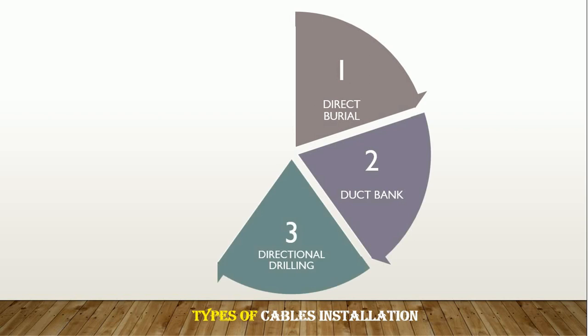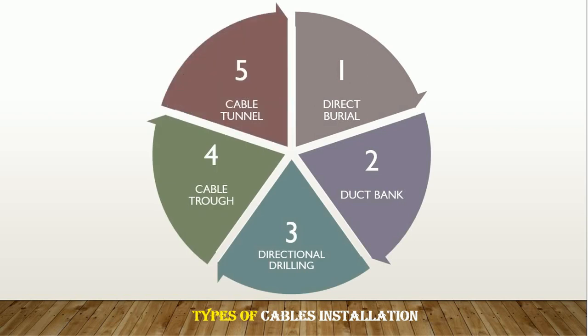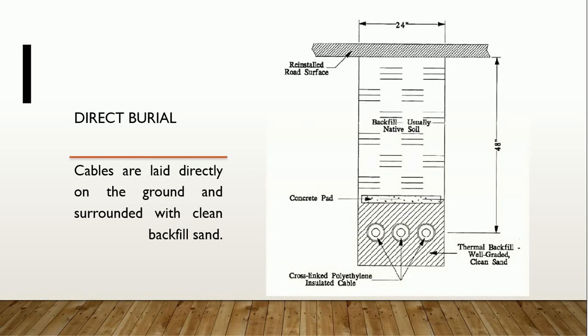Direct burial means that cables are laid directly on the ground and surrounded with clean backfill sand. As you see in this diagram, there are three cables surrounded with thermal backfill or clean sand. Then there are different layers like the concrete pad, warning tape wire mesh, and the surface layer.